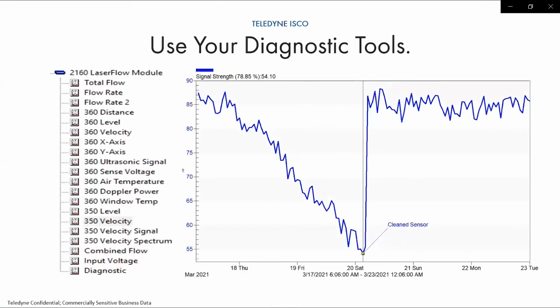Other diagnostic tools, if you have any type of signal strengths, like as mentioned before, look at the trends. This is a bit exaggerated in this example, but if you see that it's starting to drop, in this case where it was starting out at about 87%, and then all of a sudden it starts dropping down to 55%, you may have to set a reminder or an alarm that anytime your signal strengths drop below 55%, you should send somebody out there to investigate or clean. And they clean the sensor, clean the debris off of it.